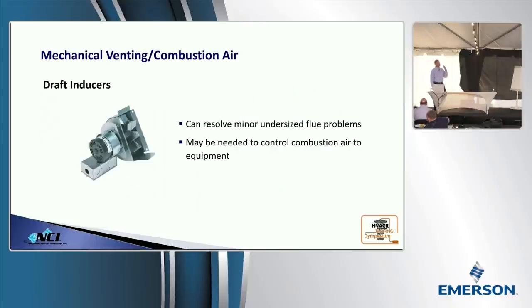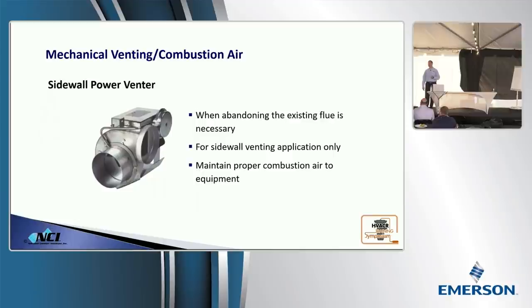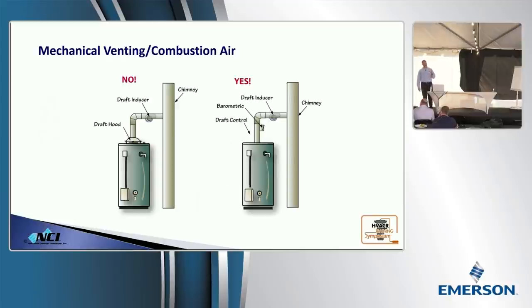There may be times you can't pressurize that space, though. So instead of pumping air in, you have to suck the flue gases out. You'll run into this on old buildings, tall buildings, where you have to put the ducts on there, a sidewall power venter. If you use one of these options, do not leave the draft hood on, because air takes the path of least resistance. What's going to happen? Is it going to suck through the burner compartment and go across the pressure drop of the heat exchanger, or will it short circuit up the hood? It'll go up the hood every time.